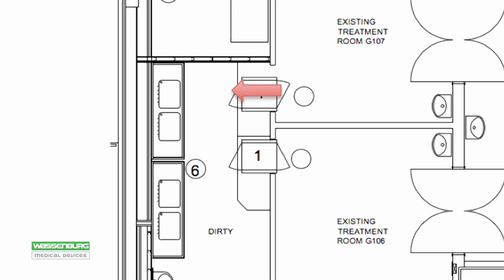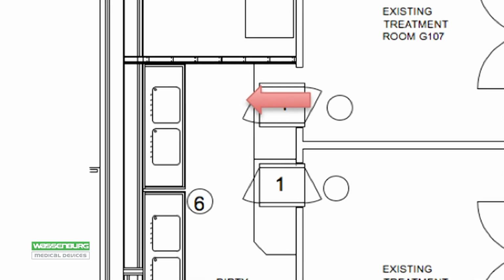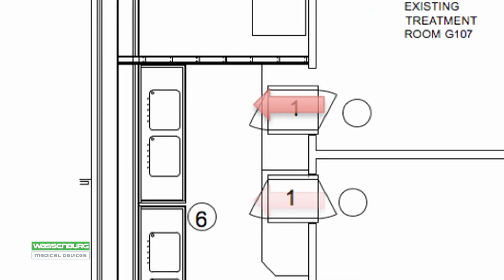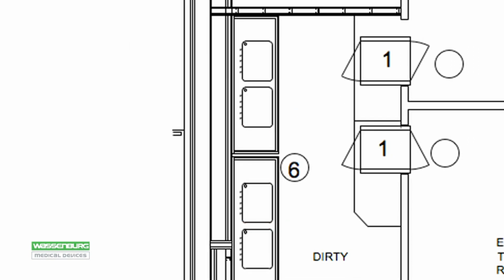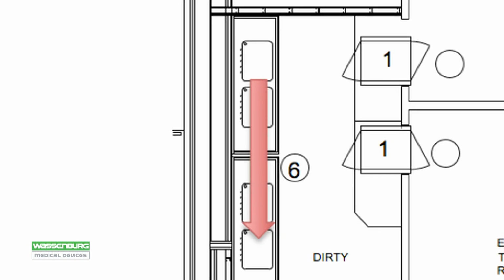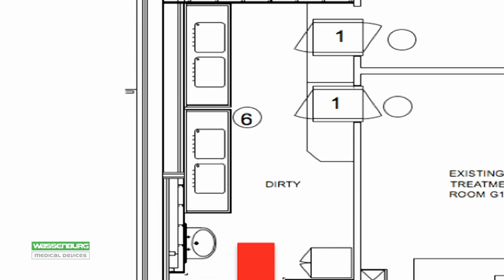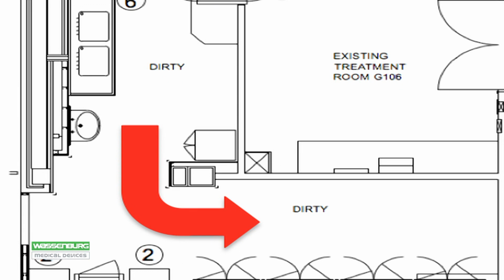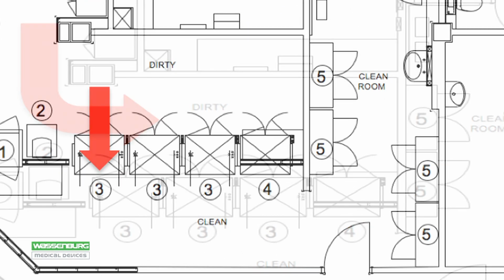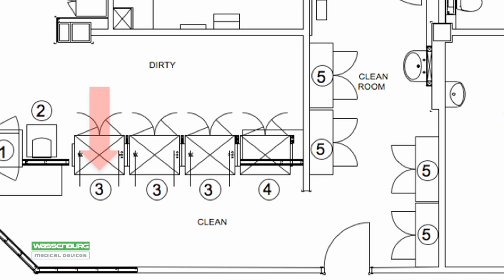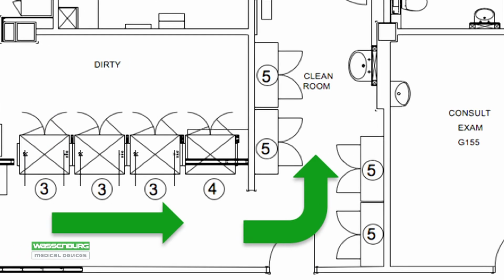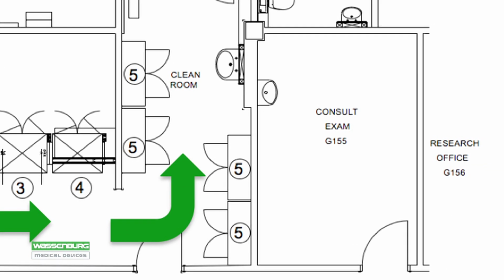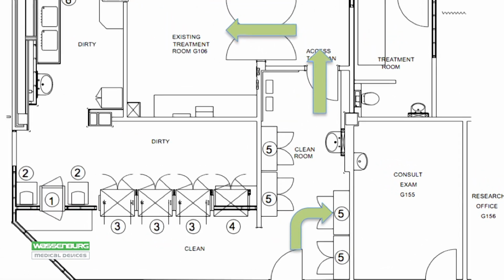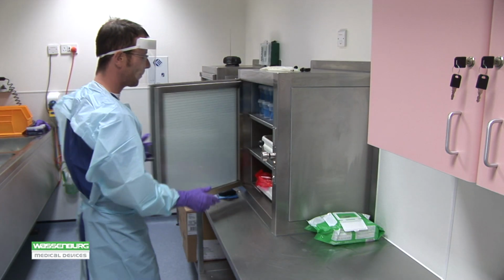Design for the upgraded unit incorporated a segregated workflow. Used scopes transferred to wash area in covered trays via interlocked hatches. 2 double-bowl adjustable height scope sinks are used to wash and rinse each scope. On completion of the manual cleaning process, scopes are transferred to the WD-440PT AERs in trays. Processed scopes are unloaded in the clean area that is maintained at positive pressure to the loading area. Scopes are either transferred back to the treatment rooms in covered trays or returned to the dry 300 cabinets for storage before next use.